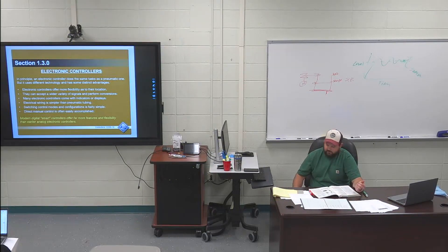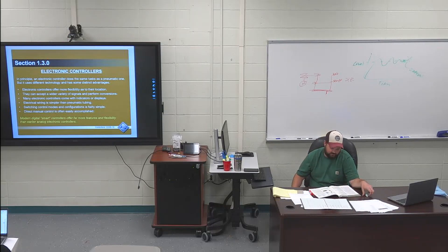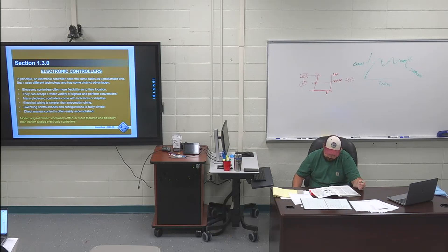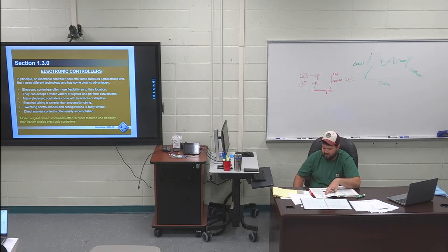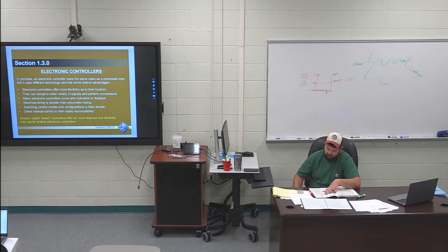Proportional control, section 132 — the second paragraph, second sentence is an online test question: 'The control slide wire sends the signal back to the unbalanced detector as feedback, which cancels the original unbalance.' On page thirteen, the second sentence is highlighted: 'With a narrow proportional band, a small movement from the set point causes a large unbalance.' These next two highlights are highly missed. My next highlight in the top right of page thirteen: 'With a wide proportional band, a large movement from the set point causes a small unbalance.' Wide proportional band — large movement, small unbalance. Narrow proportional band — small movement, large unbalance.